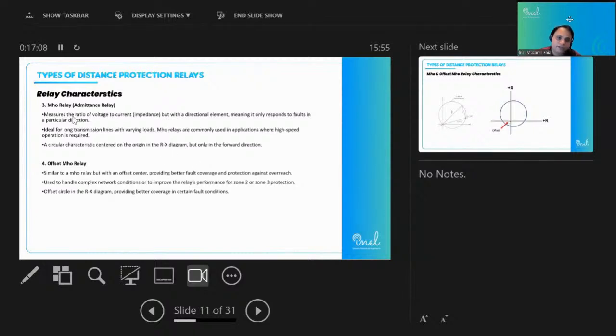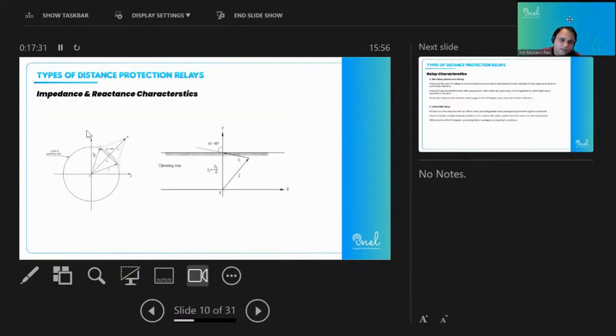And now the mostly used characteristic of the relay is the MHO, which is the admittance relay. Like if we take the inverse of the impedance of a relay, 1 over Z is equal to Y. So this is called the admittance relay. And this has some direction in nature. Like the impedance characteristic, which is equally on the right side and left side, is non-directional in nature. It doesn't depend upon whether the fault is on the front side of the line or on the back side of the line. It will operate with the preset time, whatever the direction of the fault is.